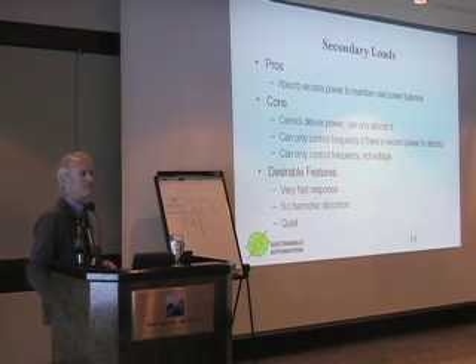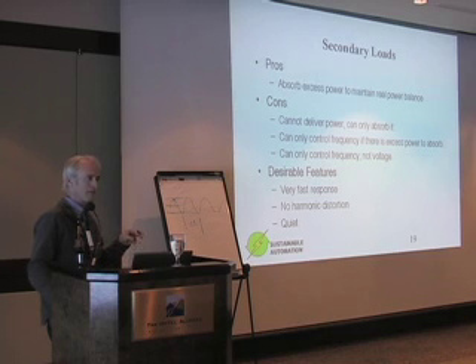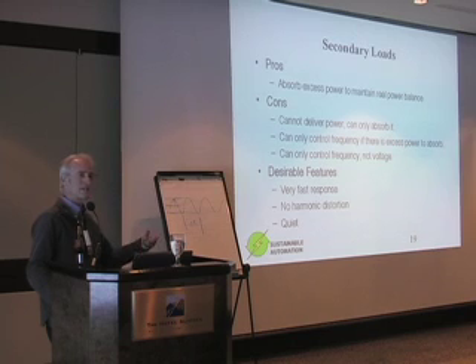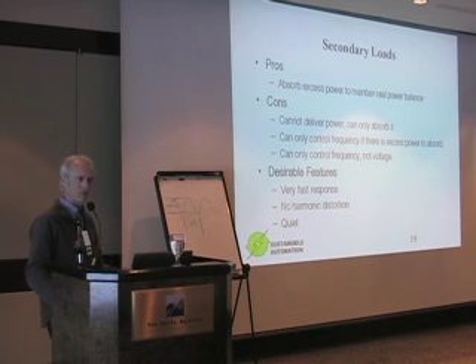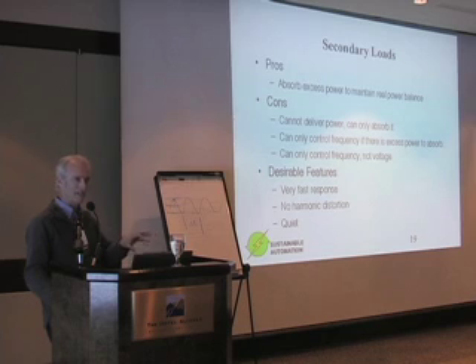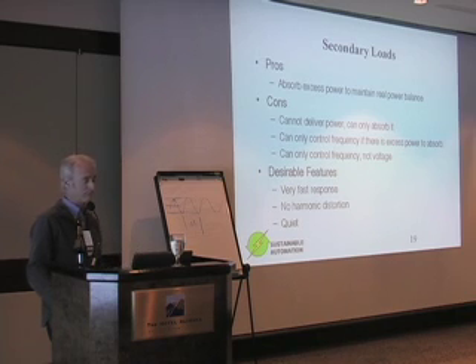Another thing about those types of power controllers, they tend to be noisy. Often you might want to implement a secondary load in close proximity to where you have the heat demand, if it's an electric boiler, for instance. And that might mean putting it in a customer facility. So you don't want something that is going to be sitting there generating a lot of electrical noise. With our approach, using solid-state switching and no waveform distortion, they're absolutely quiet. You never know it was there, so you can stick it in the utility room of a school, for instance, and no one's going to notice it.